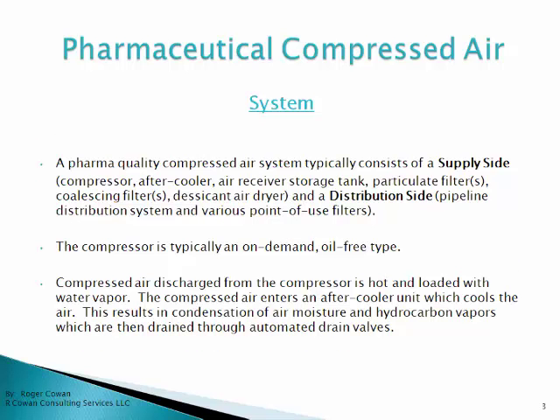A pharma quality compressed air system typically consists of a supply side and a distribution side. On the supply side, there's the compressor, the after cooler, air receiver storage tank, various particulate filters, coalescing filters, and a desiccant air dryer. On the distribution side, you've got the distribution system pipeline itself, but also various points-of-use filters.